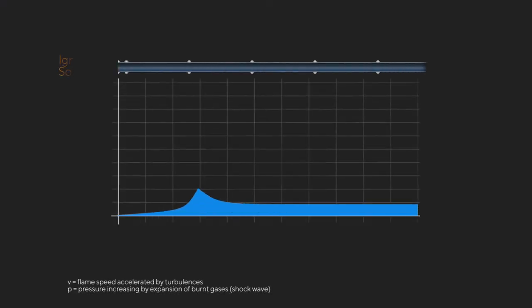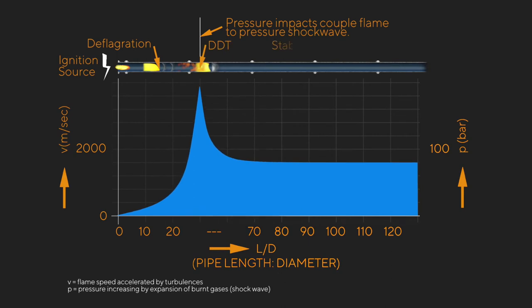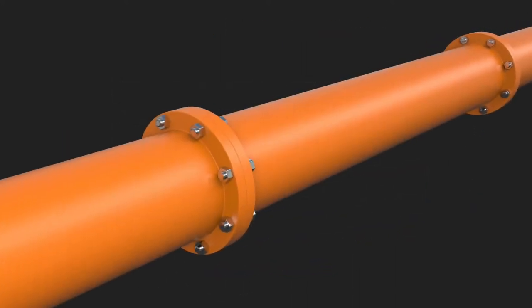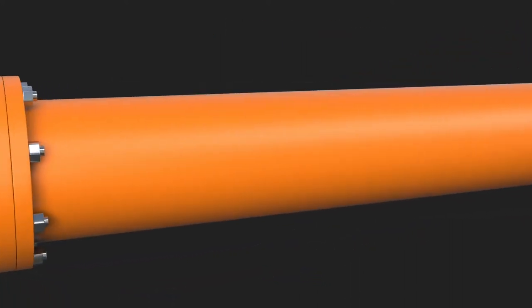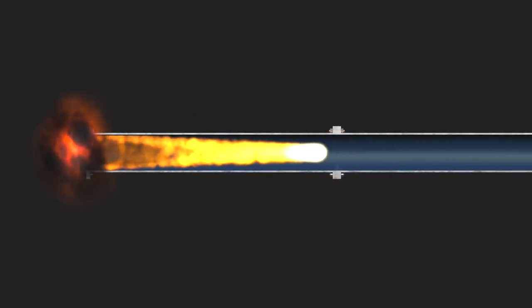However, due to the gas mixture and changes in the pipeline geometry, further unpredictable DDTs may occur, resulting in what is known as a galloping detonation. The location of the incredibly destructive forces of unstable detonation cannot be predicted with any certainty.